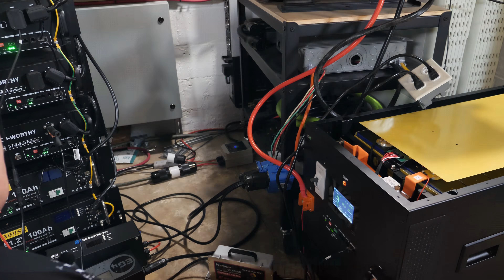That's crazy. If you want to take a look at the JK BMS software real quick, we're sitting at 51.37 volts, drawing 242 amps or 12,430 watts, somewhere around there. Cell delta is 26 millivolts, so we're still doing really, really good. Cell number 9 is our weakest right now at 3.192. Cell 16 right now at 3.219. So 16 and 13 are our highest cells right now. If you want to see all the temperatures, of course, they're all listed right through here.